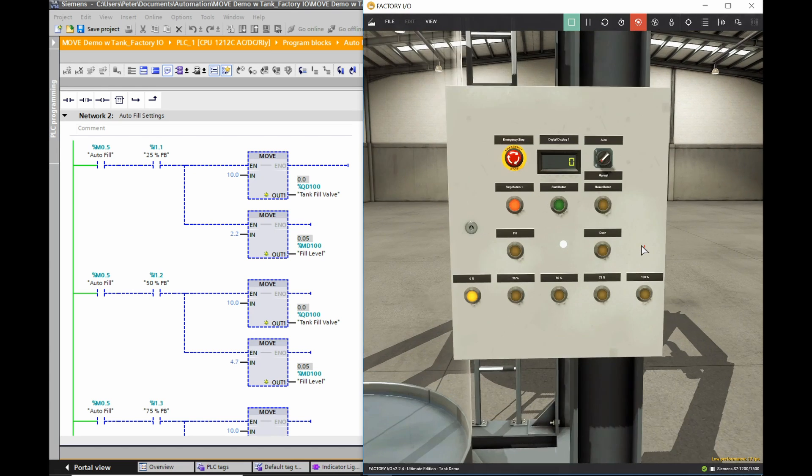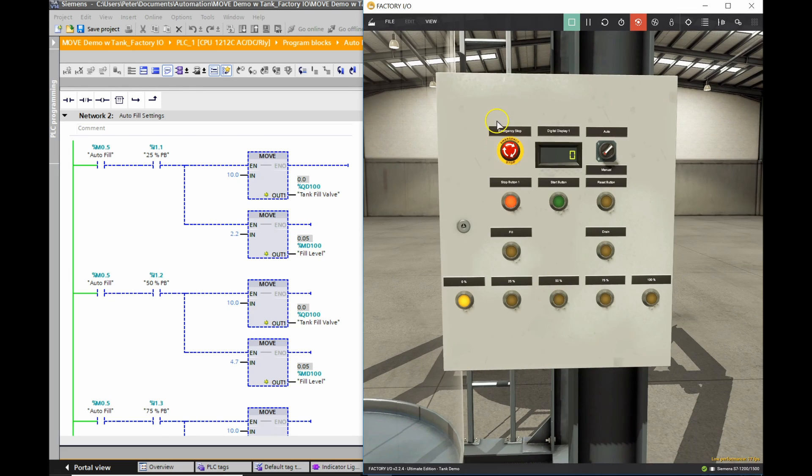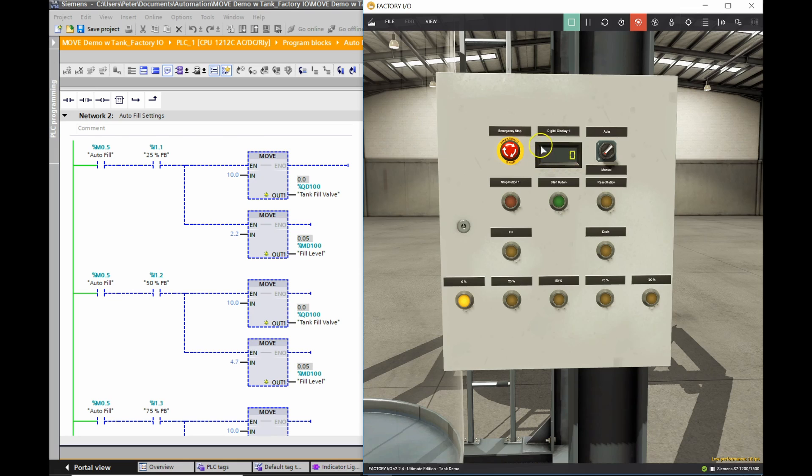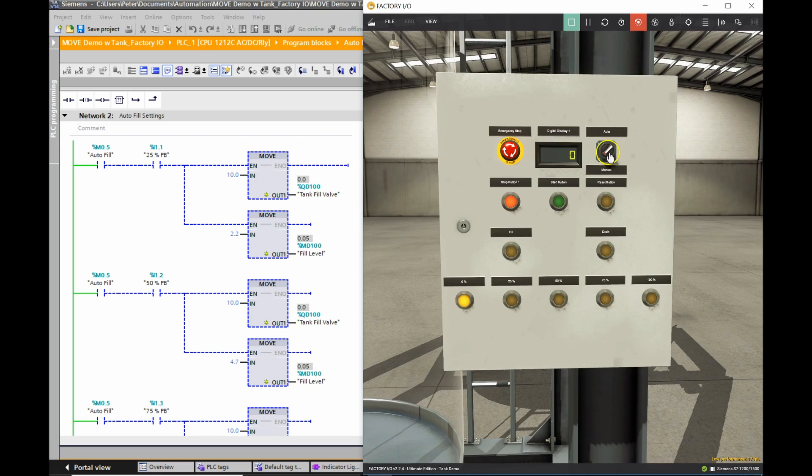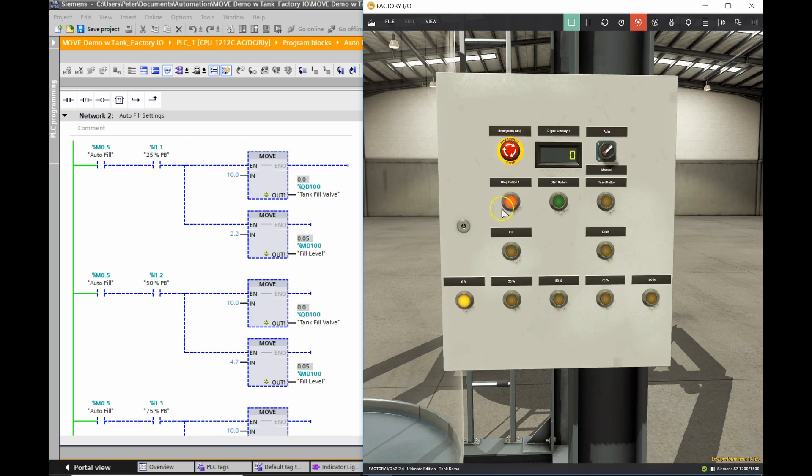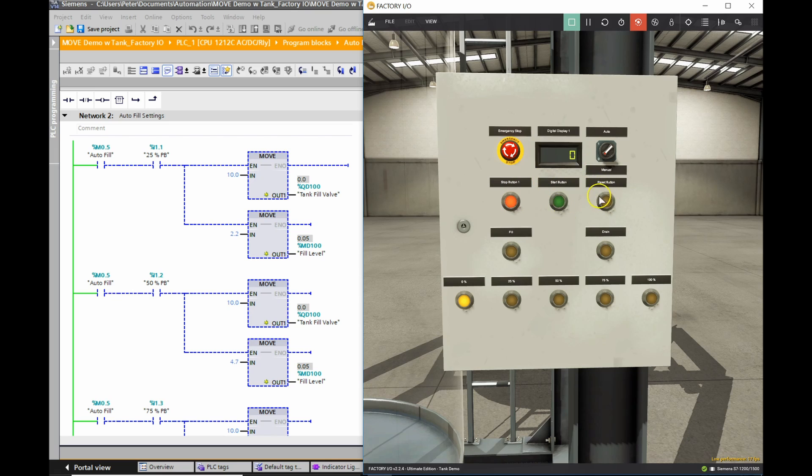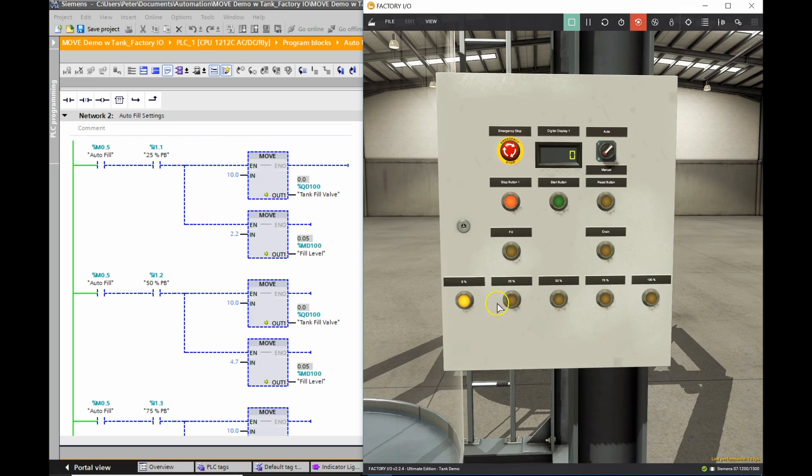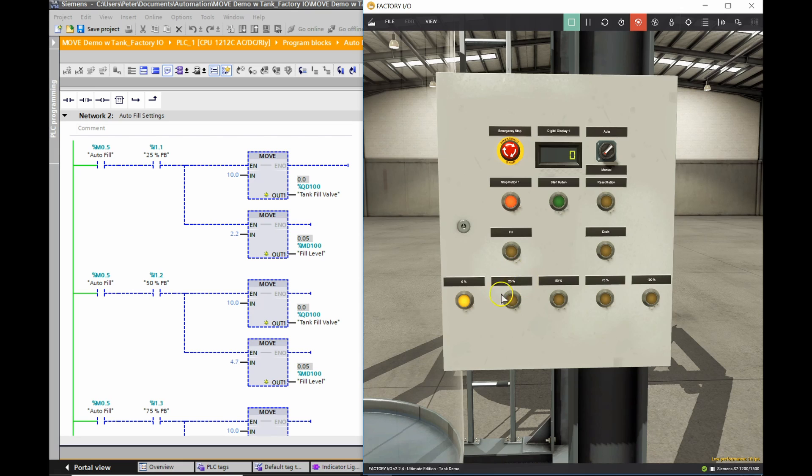I've just dropped in a box and put a number of switches. I have an e-stop here, a digital display, so in the next few videos you'll see how to take the level in the tank and have that displayed. I have an auto manual switch, so in this position I'm in auto mode, and this position I'm in manual mode. I have a stop push button with a flashing bit attached to it, a start push button, and all my other push buttons are normally open. I have a reset, then fill and drain push buttons, and these down here are indicator lights for 0, 25, 50, 75 and 100% full. But there are also push buttons, so if I press these I should be able to go to these exact levels when I'm in the automatic mode.